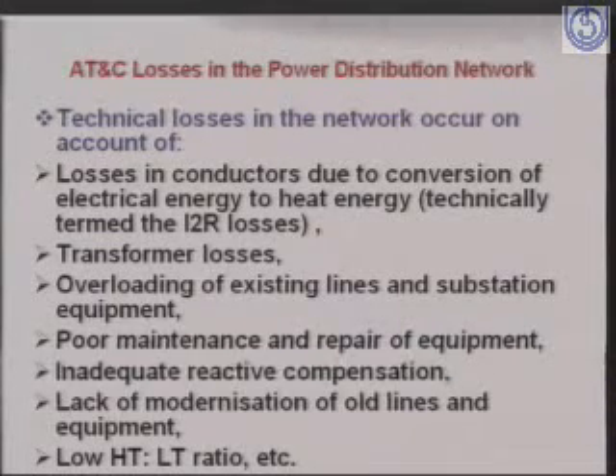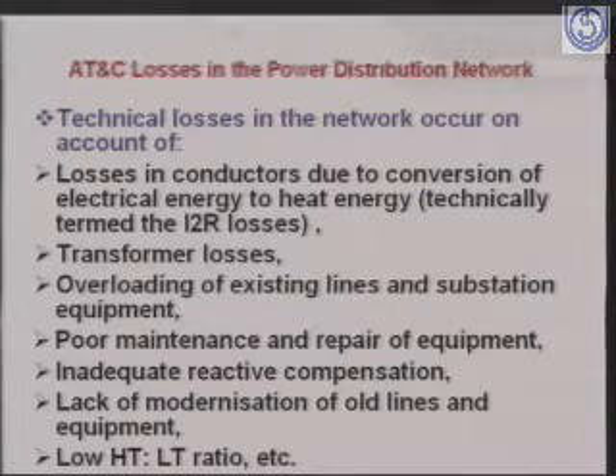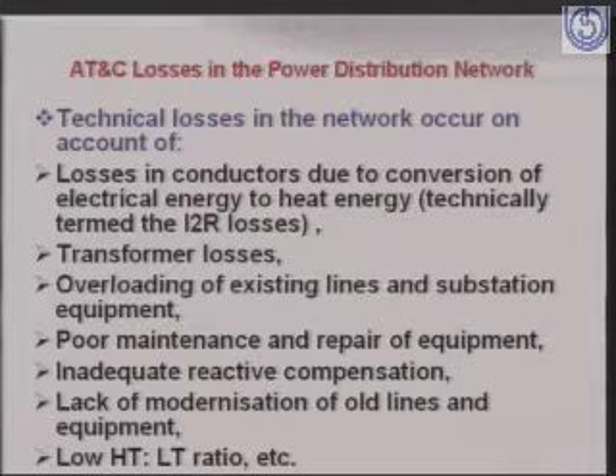There are transformer losses, overloading of existing lines and substation equipment, poor maintenance and repair of equipment, and inadequate reactive compensation. If you don't have sufficient power factor capacitor correction, high lagging reactive power causes line losses and transformer losses to increase. There is also lack of modernization of old lines and equipment, and low HT to LT ratio, where we have less high tension lines and more low tension lines.